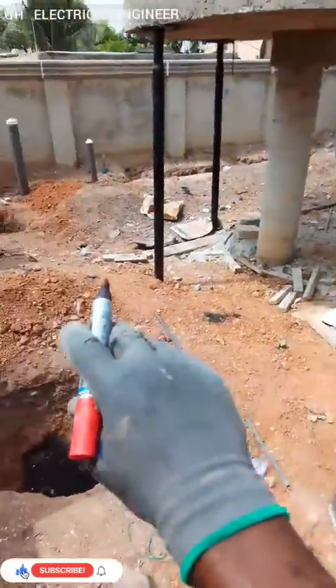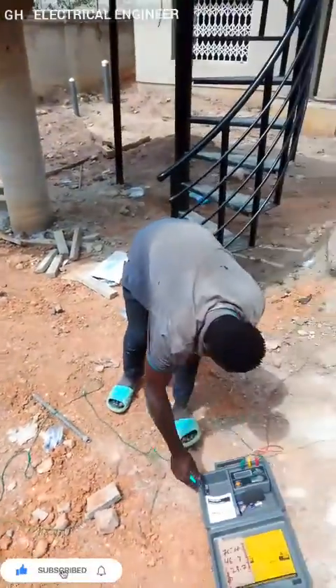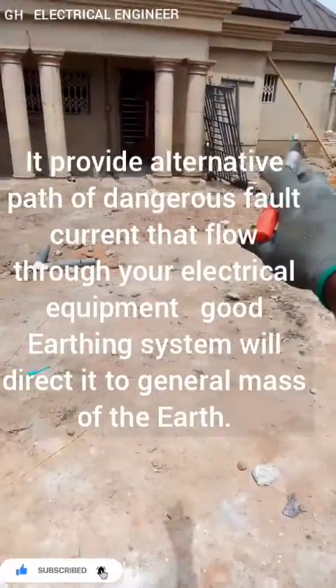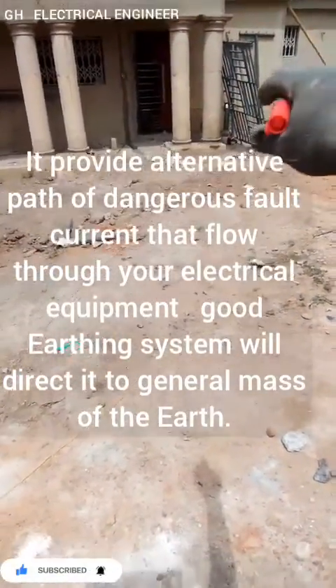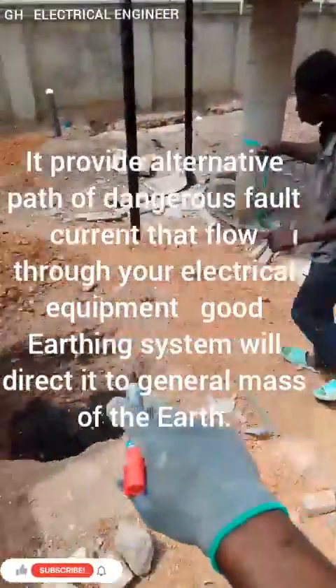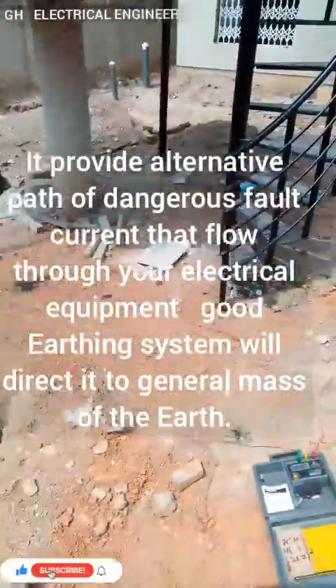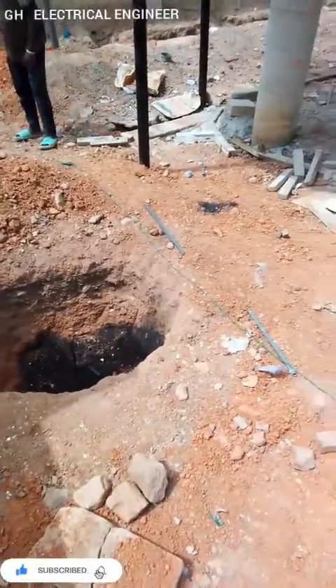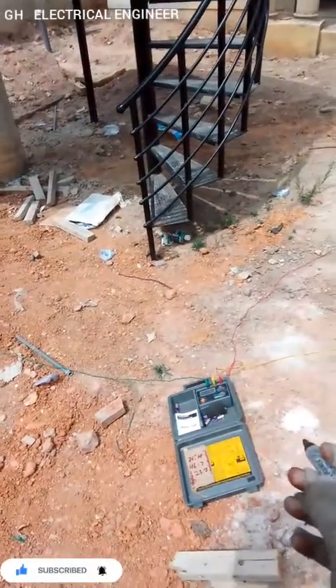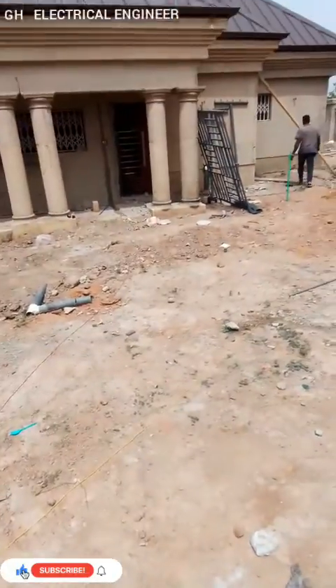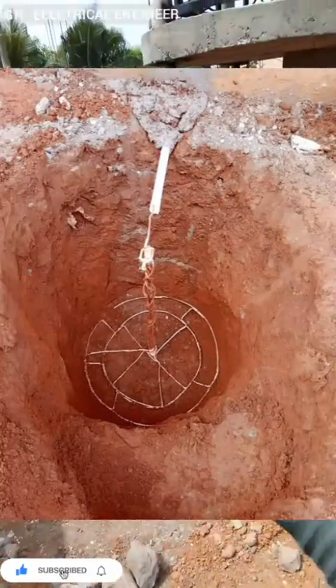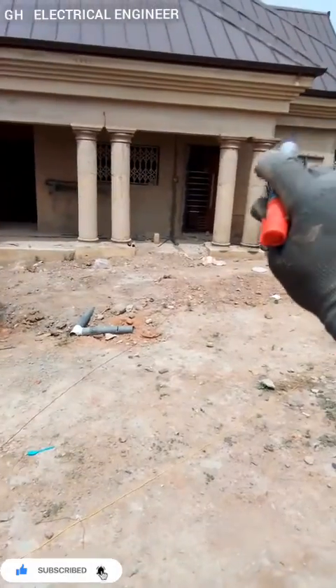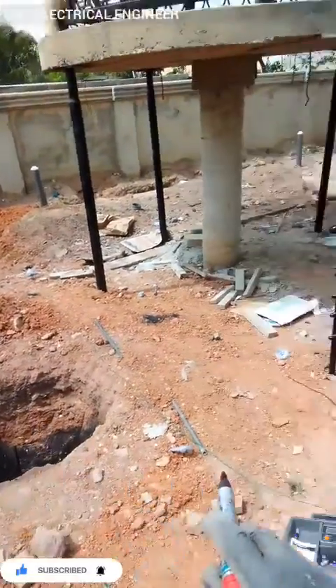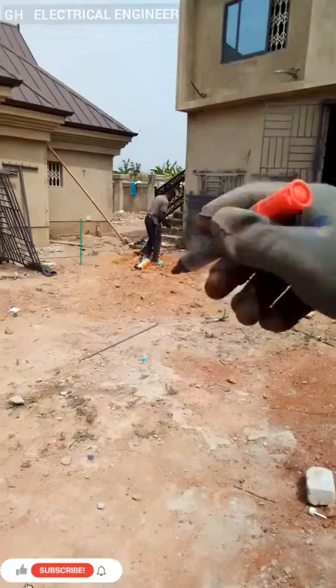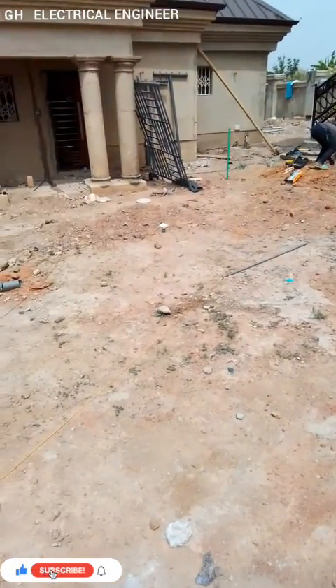An earthing system provides an alternative path for dangerous fault current to flow through, into the general mass of the earth. Any fault in your electrical installation, or in your fridge or deep freezer, if you happen to be touching it, that power would flow through you. But with a good earthing system, that fault current flows back to the earthing system instead of shocking you. The main building earthing installation goes right here, and the second story building goes to the other side of the earth rod.